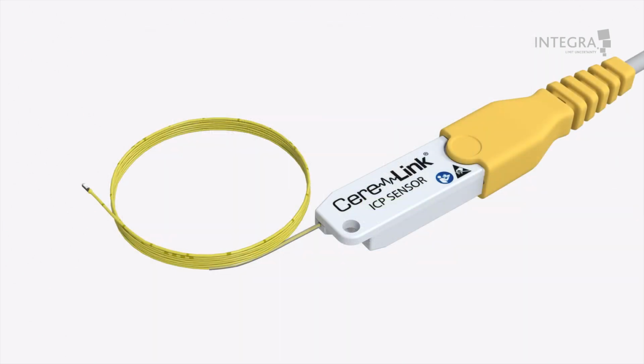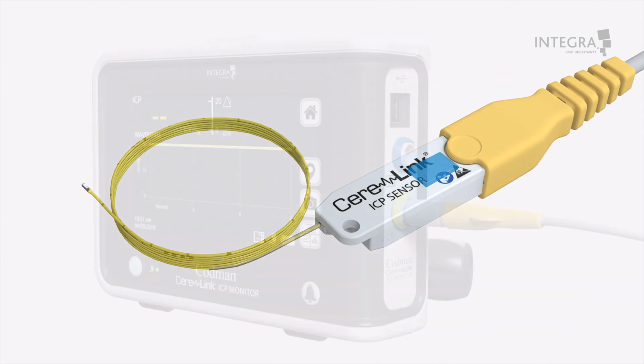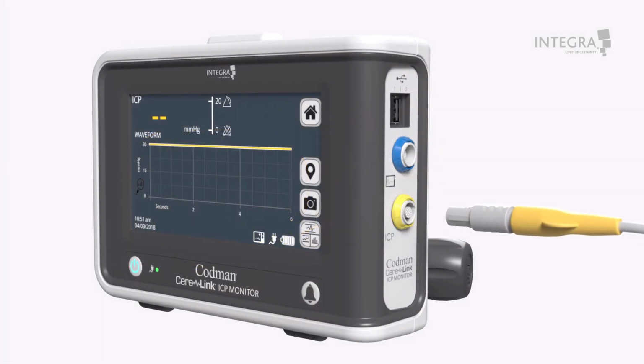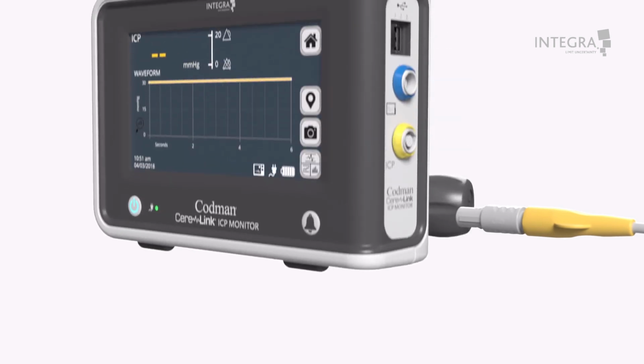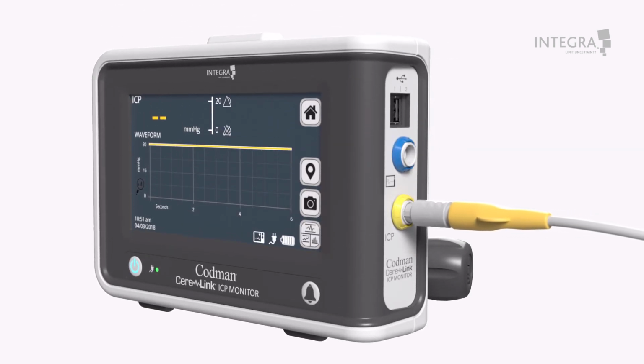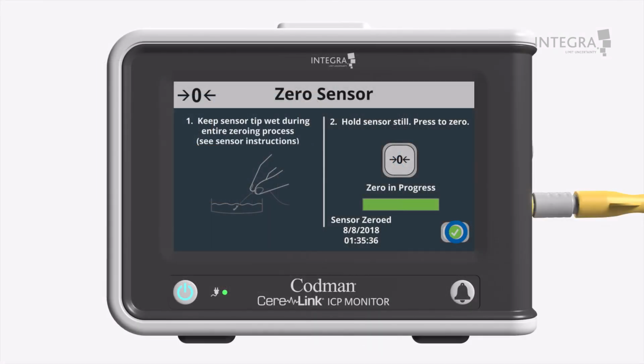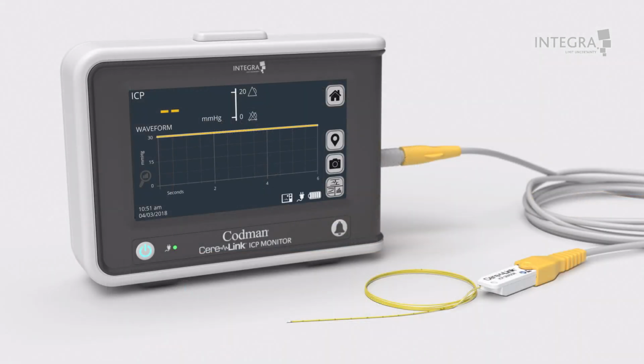During this zeroing process, the ICP monitor automatically stores the 0 reference value in a memory element embedded in the ICP sensor. This feature allows the user to reconnect the ICP sensor to the same or a different ICP monitor without having to readjust the 0 reference value. Press the Accept button on the lower right portion of the screen to return to the main screen. Now the ICP sensor is ready for implantation.